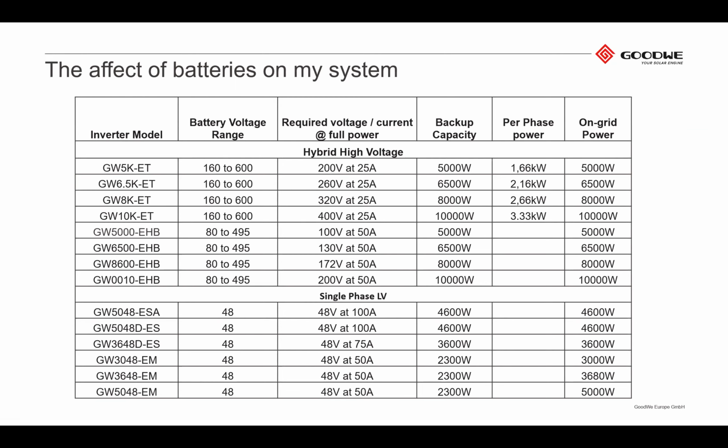When we only have batteries available, our capacity is limited by our batteries and the charge and discharge capability of the inverter. So we'll see here 4.6 kilowatts. When the grid is unavailable and all we have is batteries, we are quite limited to that 4.6.